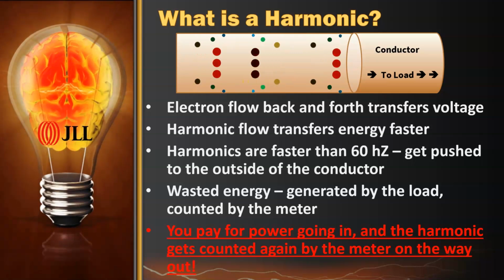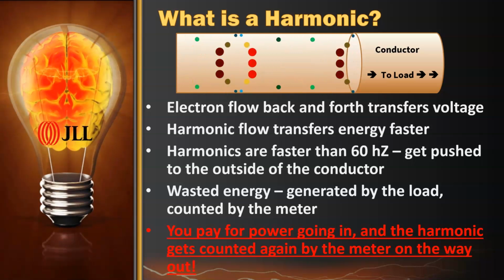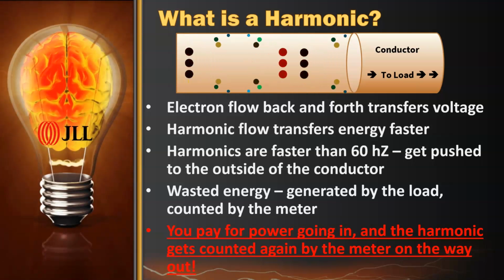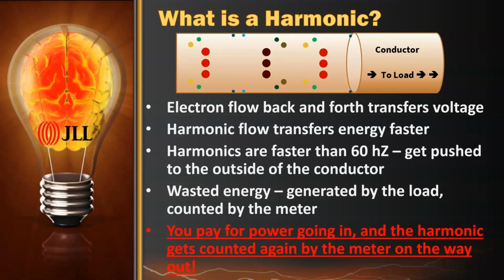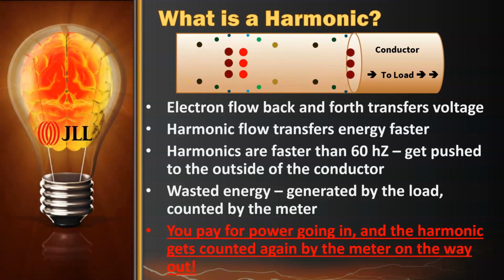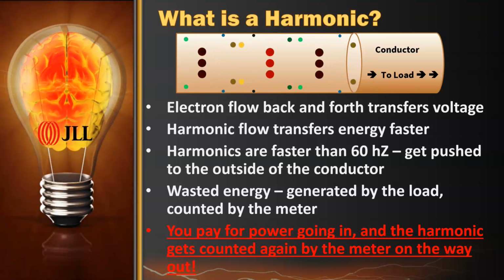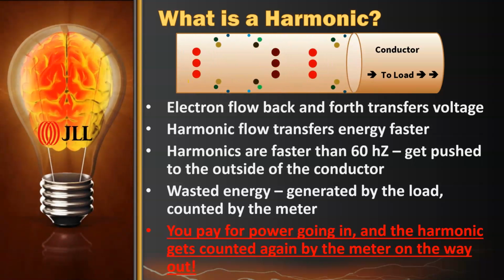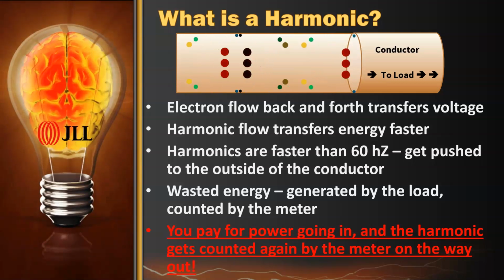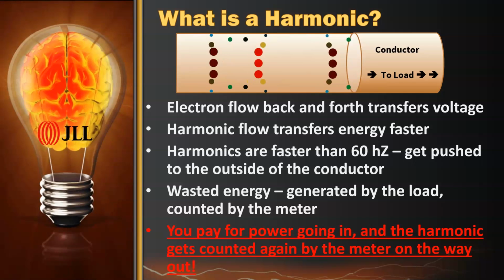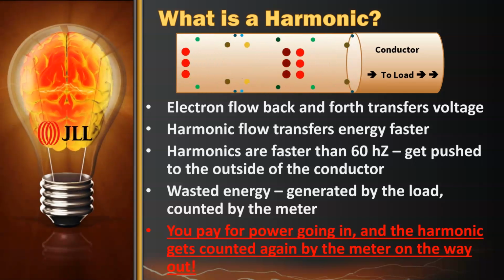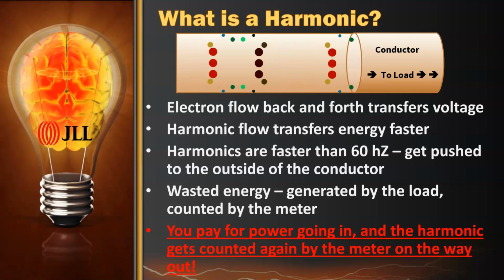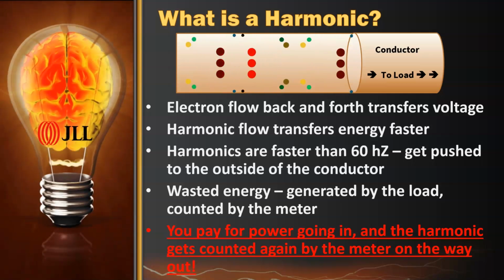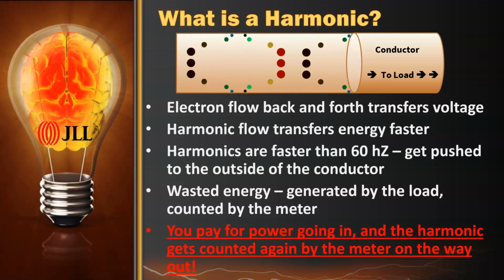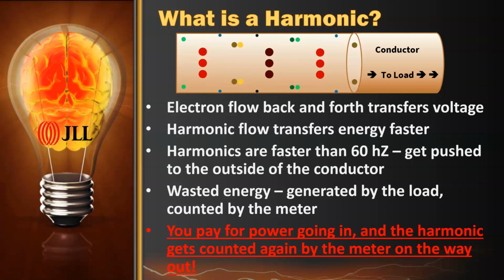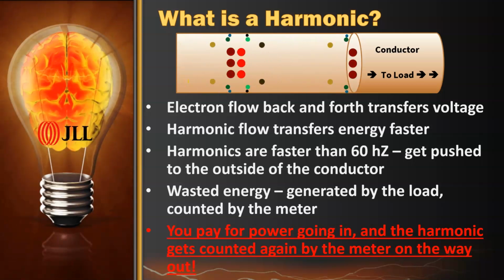And I can actually replicate that. If I take a third, a fifth, and a seventh harmonic, I can make that sound, and it sounds exactly like the annoying buzzing that you hear sometimes in electrical rooms. Every once in a while, you're going to see that the electrons sort of line up with one another there. And when that happens, because it's happening 60 times a second, because that's the primary waveform speed, that energy inside that conductor spikes, and when it spikes, it creates a spike in the magnetic field around the conductor. That's very handy for us from a measurement point of view. I'm going to talk about that in a minute.